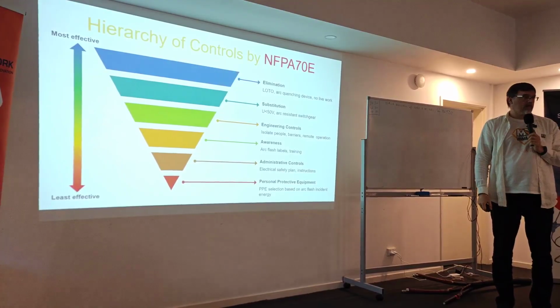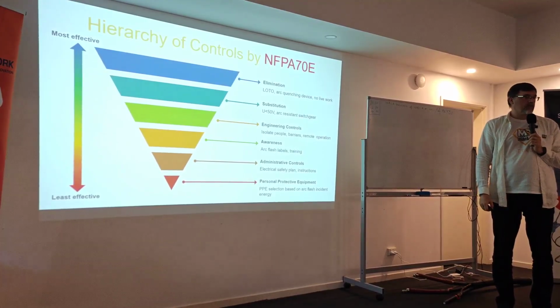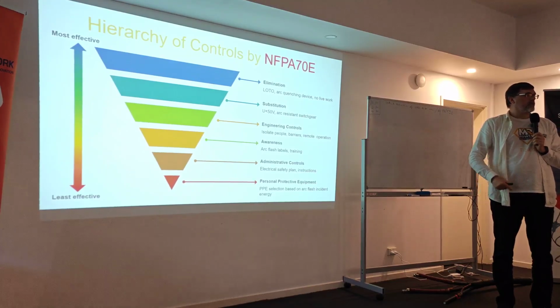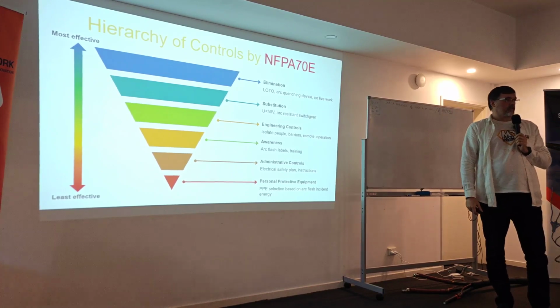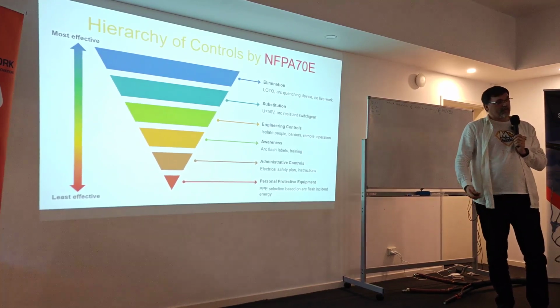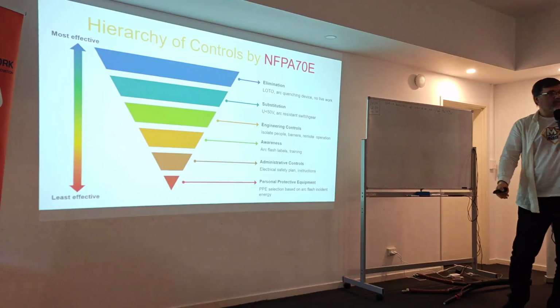Because the allocation that we have, where there are like 200 calories plus, and this is not an engineering or calculation error. It is 200 calories plus. That's what they have. And you cannot select PPE for something like this. Just because you think you can select PPE, you can't. So we have to go down to the point where you actually can do this.